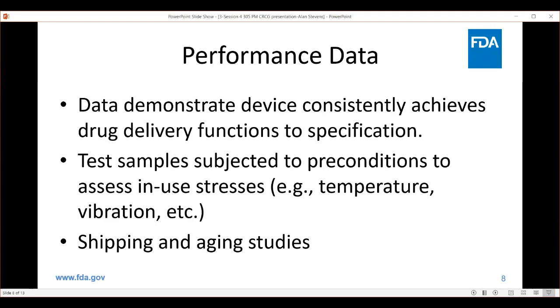And these are key to consider. For example, I mentioned assessing preconditions or in-use stresses. From an engineering standpoint, we're thinking about how the product is being used and what stresses it's going to be subjected to in use, and we're expecting that the design verification studies are going to cover or simulate those exposures. So the ISO standard is one way of doing that for injectors. For prefilled syringes, I mentioned that the 11040-8 standard wasn't recognized. That standard does provide a lot of good information about the type of requirements that need to be met, but it doesn't go into the level of detail about, for example, the in-use conditions that you might want to subject the product to.